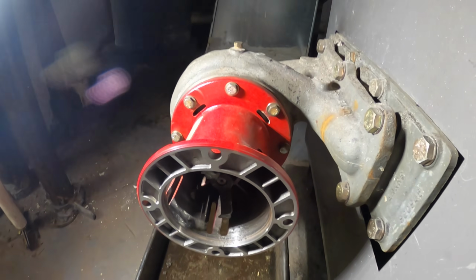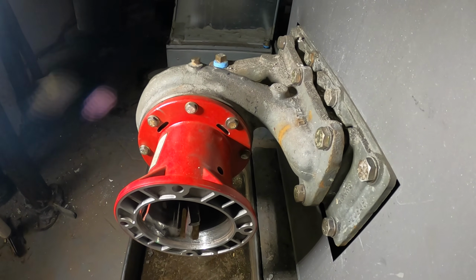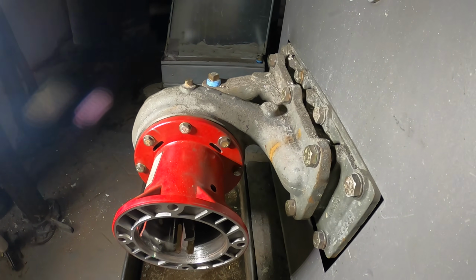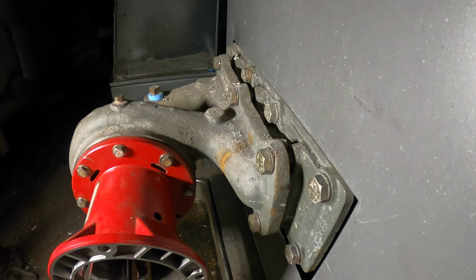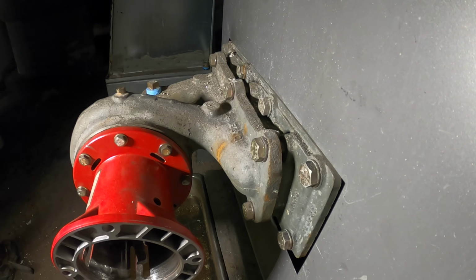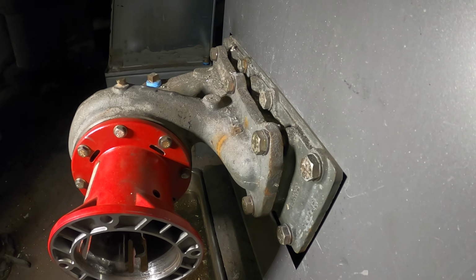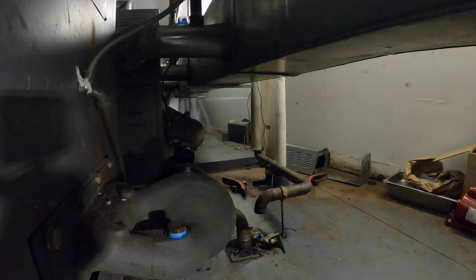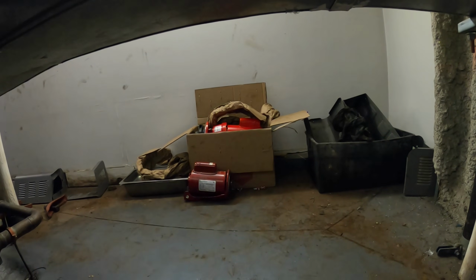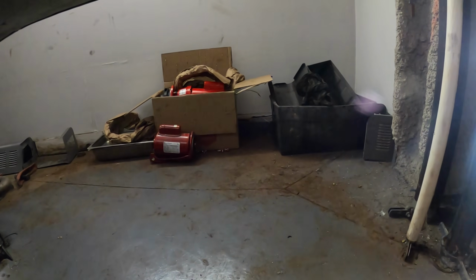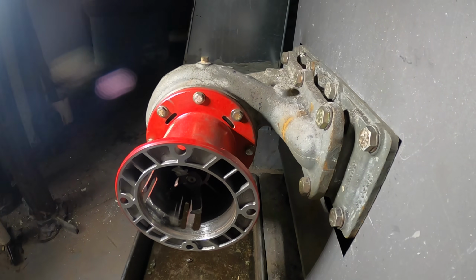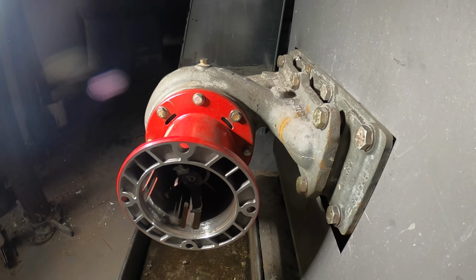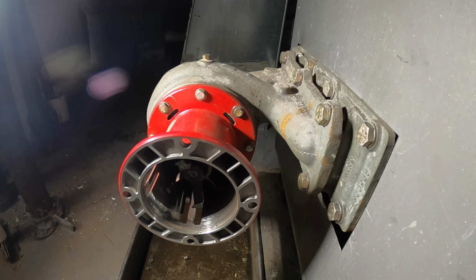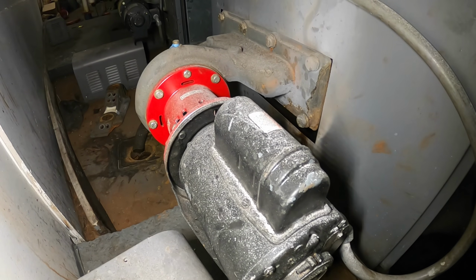So over here, here's the pump that needs to be taken out, but we need to change this piece here, the pump header. We can't get this pump out of there, and it's just time for this thing to go. They want it done right away, and this boiler, along with number 5, serves floors 7 to 17, which is much more important. We're actually going to take apart the pump header from boiler 1 or 2 and install it here. We do have a new pump back there — maybe we'll put the one from that boiler, or maybe put the new pump on the other side. Let's shut down either boiler 1 or 2, drain it, and pull everything out. We've got this pump here, and it sounds horrible.